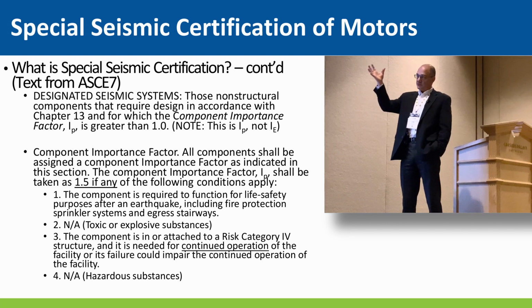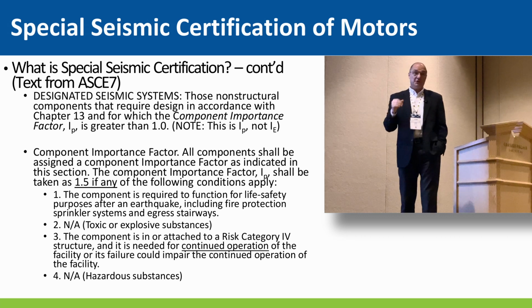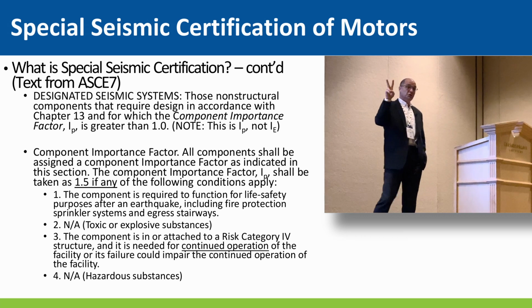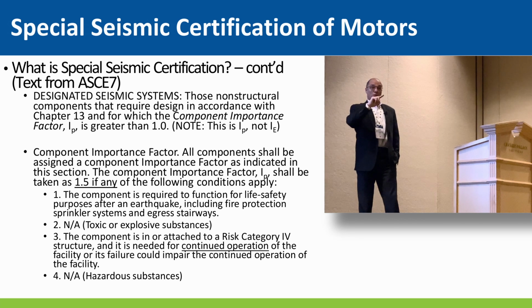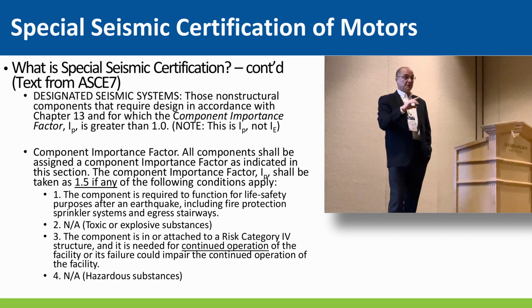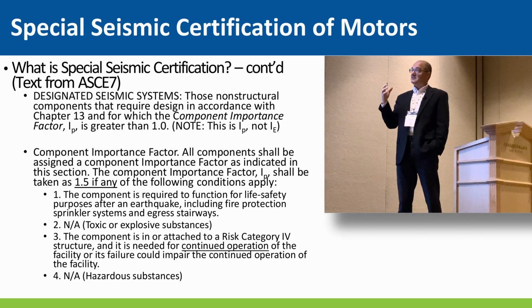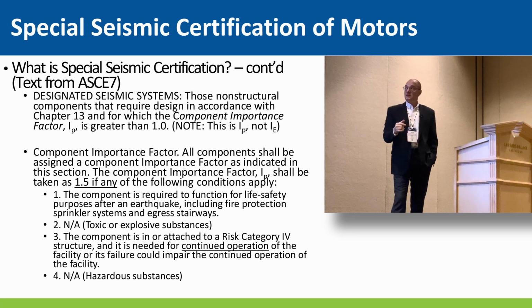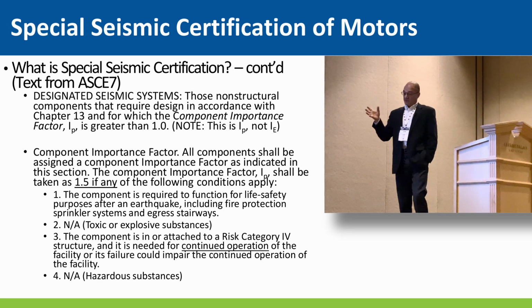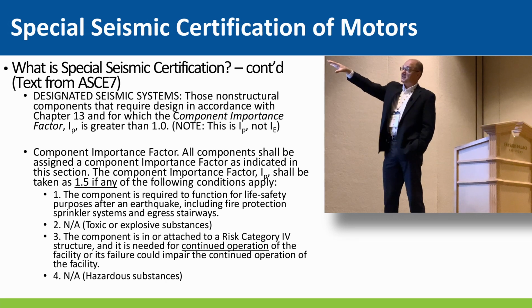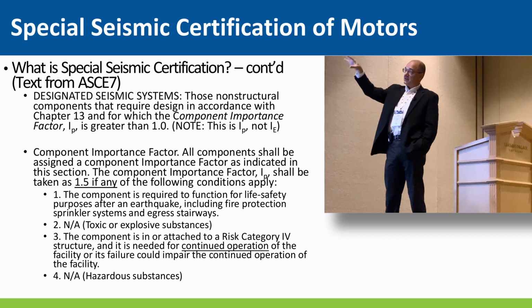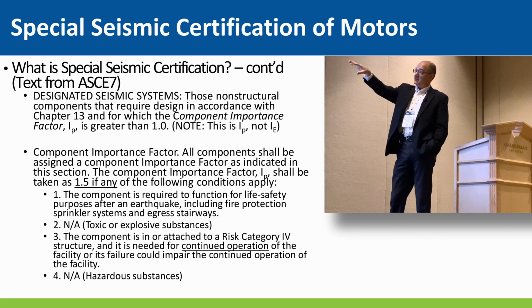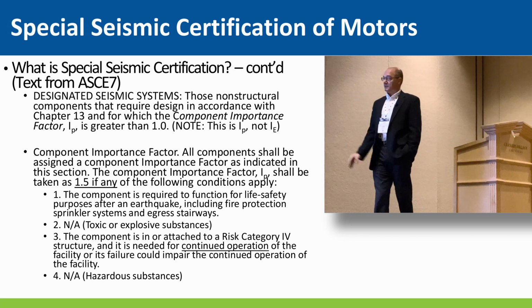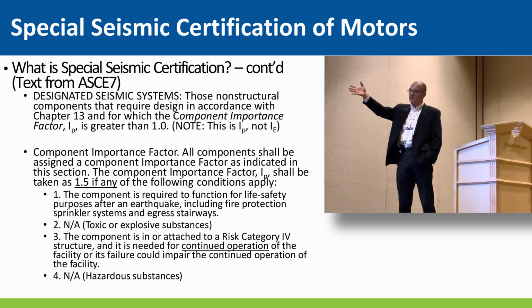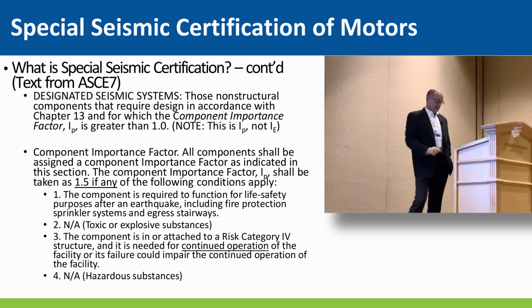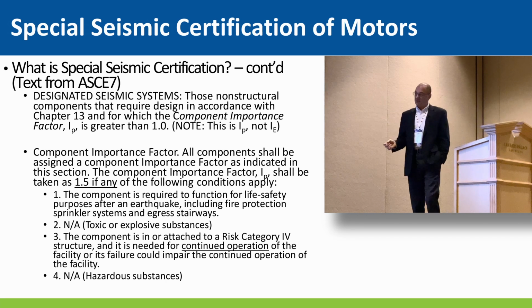And the confusion lies with this Ip because it's not Ie. In the code, there are three Ies, which is for the building, and only two Ips for the component, which is 1 or 1.5. If it's 1.0, you don't need to deal with it. If it's 1.5, that defines that the equipment has to be functional after the earthquake. And it goes on to say that all components shall be assigned a component importance factor, and it's taken as 1.5 if any of these apply. The one we're talking about is that it's required to function for life safety purposes after an earthquake. So once again, we have a little more ambiguity.